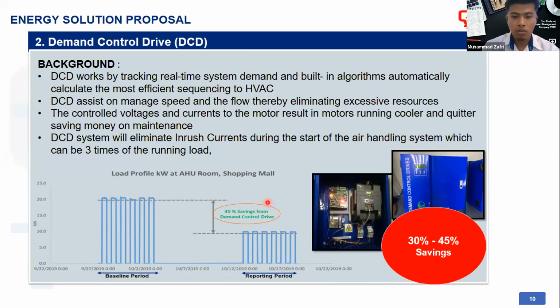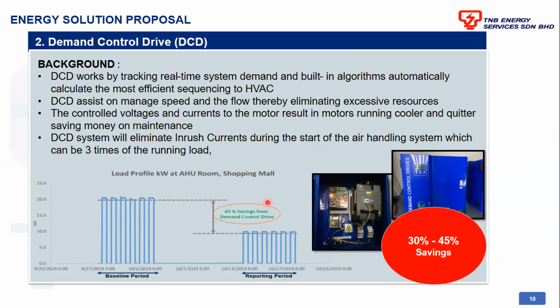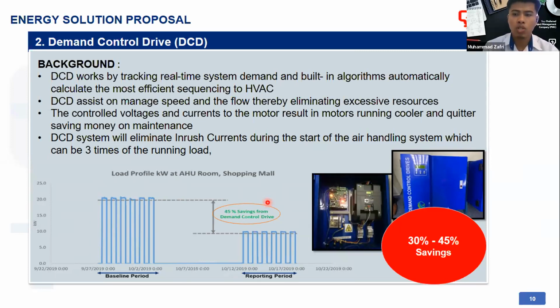It also controls the voltage and current, and improves the in-rush current. Based on our study, at one shopping mall we installed a DCD at their AHU, and it contributed about 45% saving to the AHU operation. So on average, the range is about 30 to 45% saving for the AHU. This kind of technology is good for motorized systems basically.